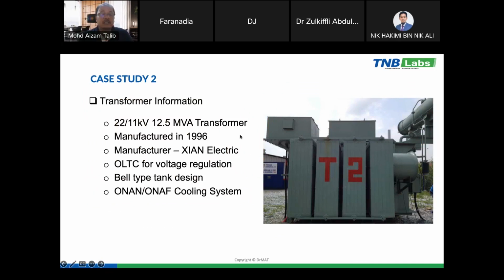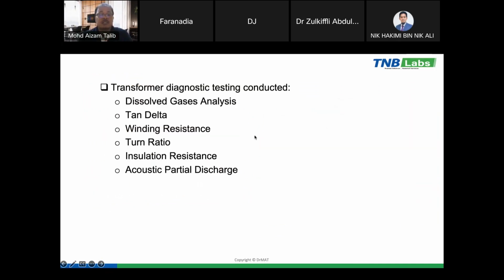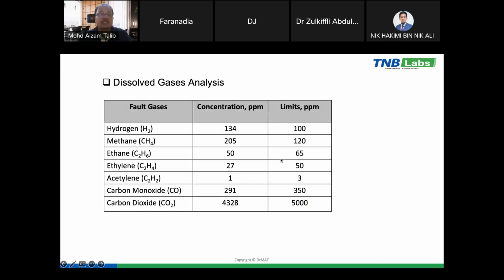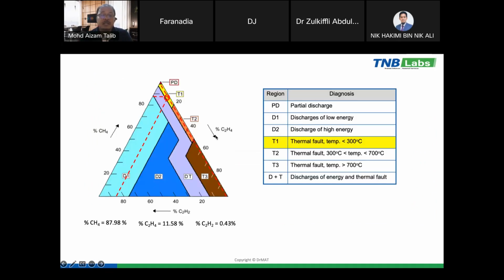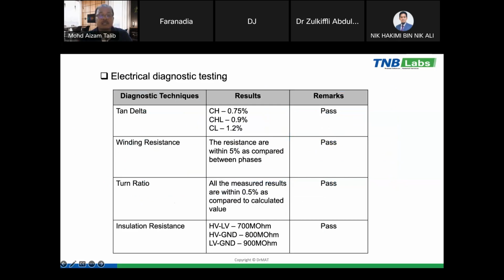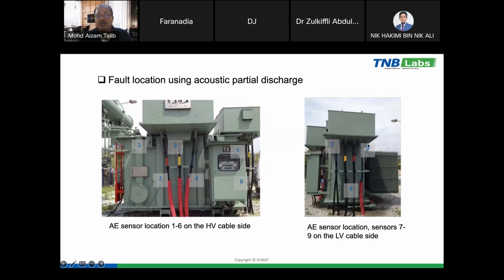Okay, the other case study, these are small distribution transformers. We did a complete test on the dissolved gas analysis, and also electrical routine testings. We got a gas reading that said when there is a presence of high hydrogen, it means there is a possibility of partial discharge occurring in the power transformer, and also more on the overheating of the transformers. And then through this duval triangle, the interpretation said there is a thermal fault in the transformers. The electrical diagnostic testing, or routine testing, had passed, but we decided to pinpoint the possible locations of the high gas generation.